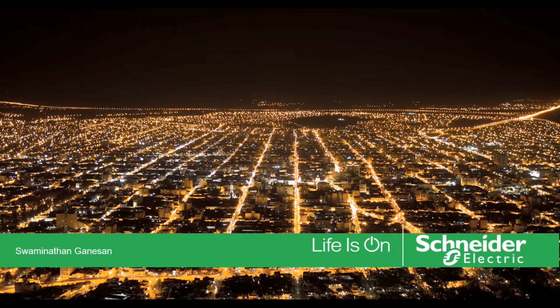In power generation, it was a combined cycle power plant. In combined cycle power plants, gas turbines and steam turbines are there together. Gas turbines are not self-starting, so you need to turn the gas turbine using a synchronous machine. The generator and turbine are coupled together, so you power the generator, and the generator runs as a motor and turns the turbine. Once it reaches 75% of its nominal speed, the turbine will be fired. Then the power supply to the generator is taken off, and it starts to produce alternating current.